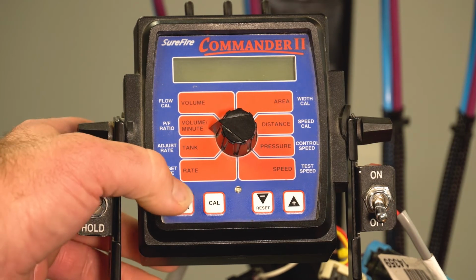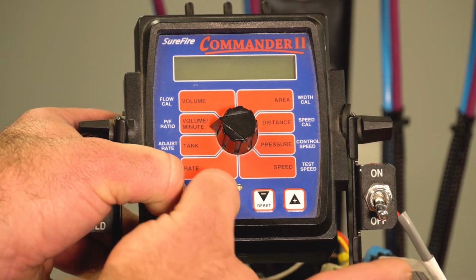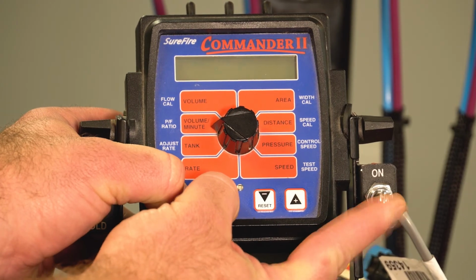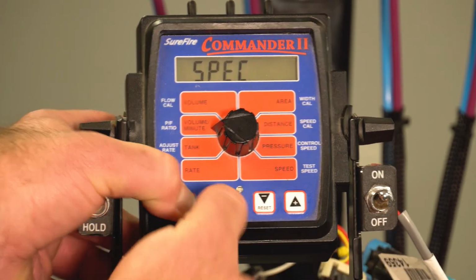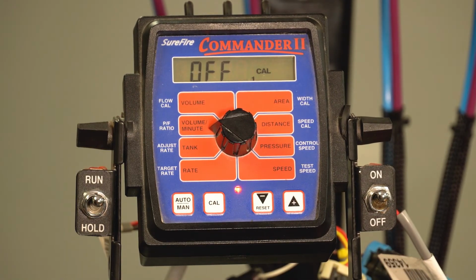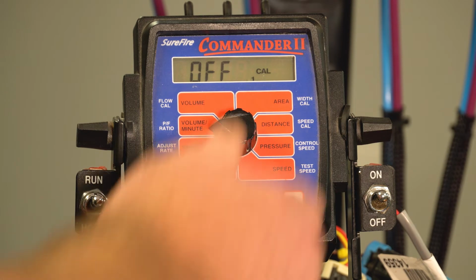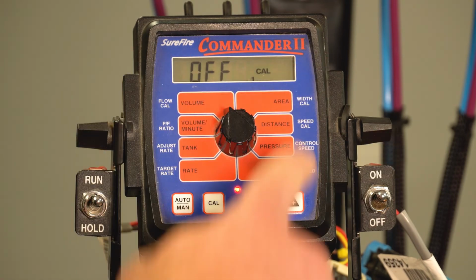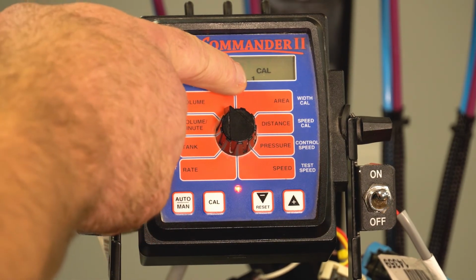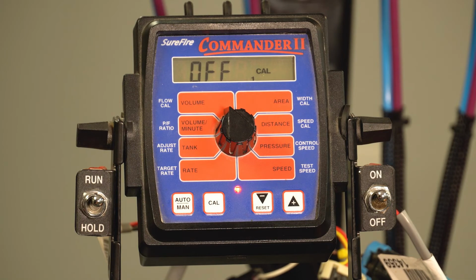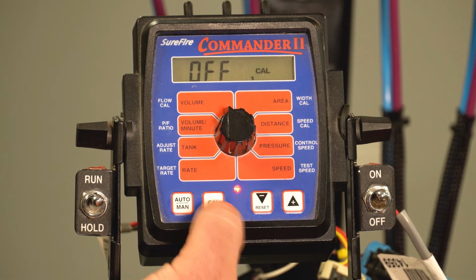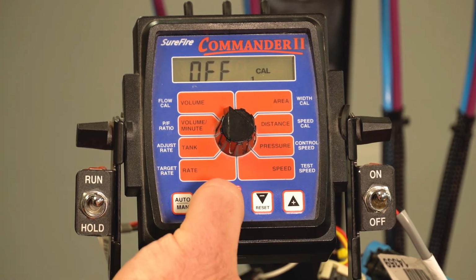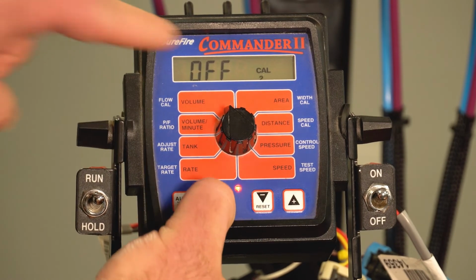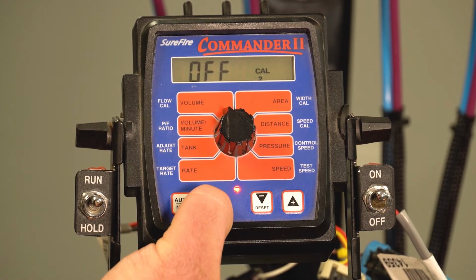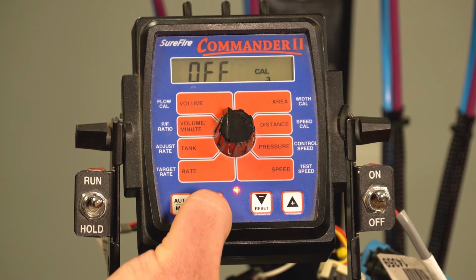So you have to hit the auto man button and cal button at the same time while flipping on the power. And SPEC, S-P-E-C, will come across the screen indicating that we're in special calibration mode, and it will show anywhere you click, basically, that we're in special cal 1. That's page 1 of the 3 pages in special cal. The way to navigate through there is to click the cal button. It will take you to page 2, and then it will take you to special calibration page 3.